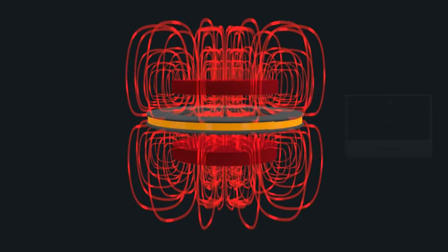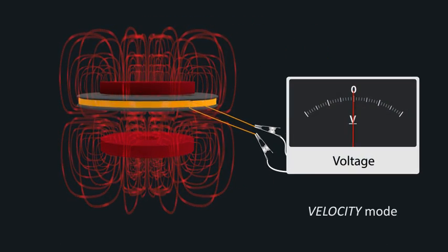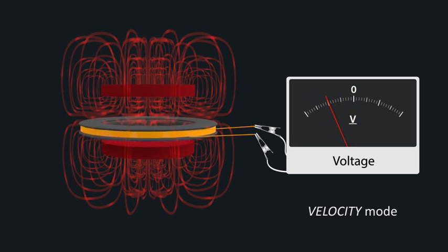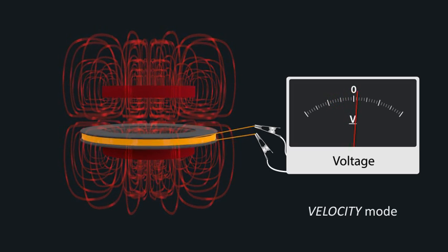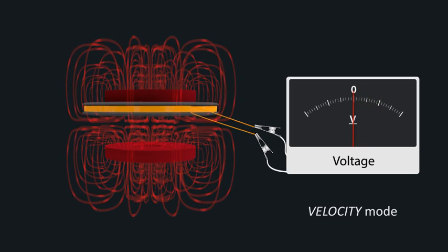The first, called velocity mode, uses an electric motor to move the coil through the magnetic field at a constant velocity. This movement induces a voltage in the coil that is exactly proportional to the field strength. Measuring the voltage indicates the field strength.